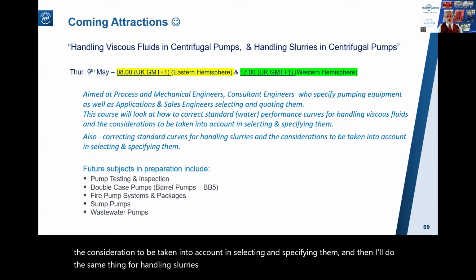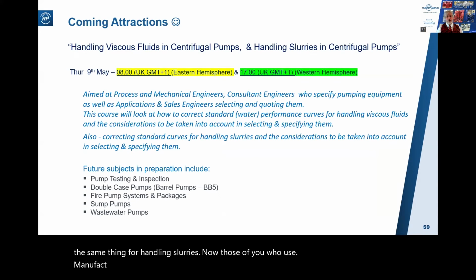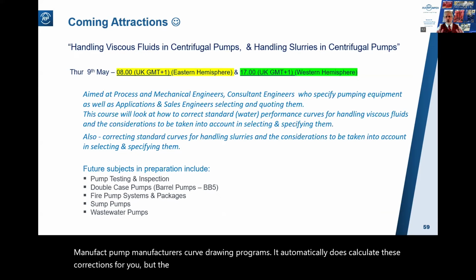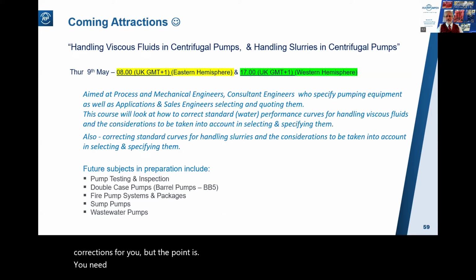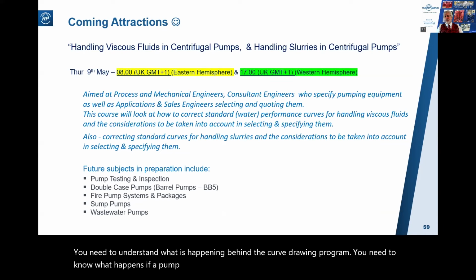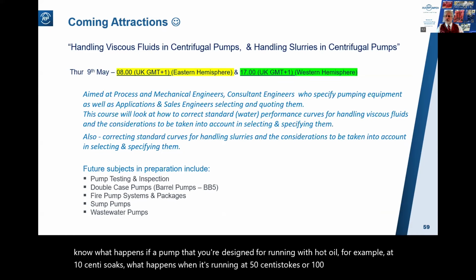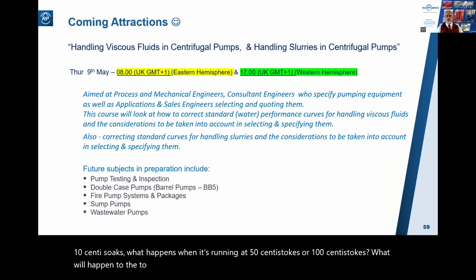Now, those of you who use pump manufacturers' curve drawing programs, it automatically does calculate these corrections for you. But the point is, you need to understand what is happening behind the curve drawing program. You need to know what happens if a pump that you've designed for running with hot oil, for example, at 10 centistokes, what happens when it's running at 50 centistokes or 100 centistokes? What will happen to the performance curve?